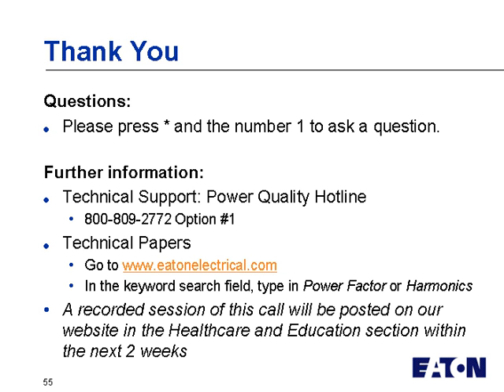So if you go out and measure for an hour, what's the chance of that hour being either the heaviest or the lightest or somewhere in between load? And really, are you going to correct the power factor based on the utility bills or just that measurement? I typically like to say that you do a combination. First of all, we do the screening with the bills just to see if you're even paying a penalty. And then as you actually apply the solution, you really have to look into more detail, as you mentioned, Jack, and that is really to look at whether or not you need fixed or switched.